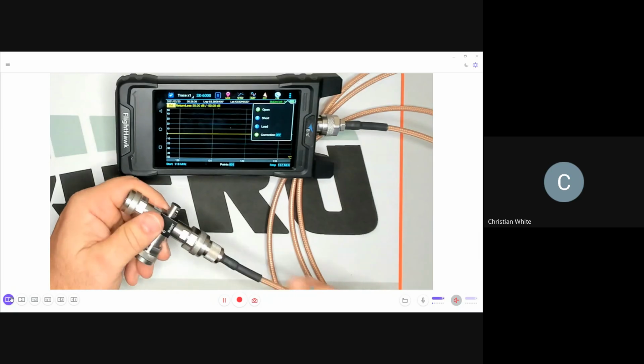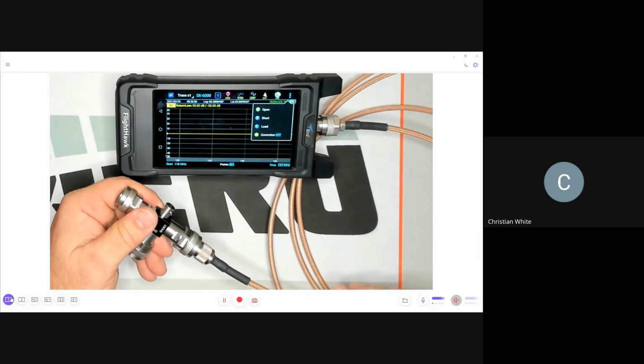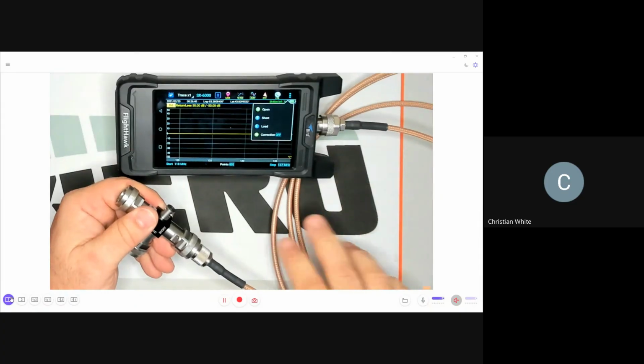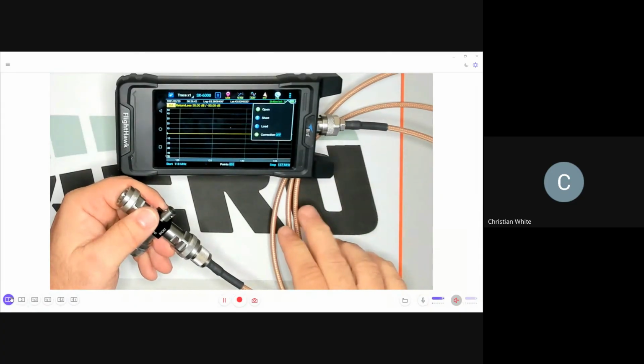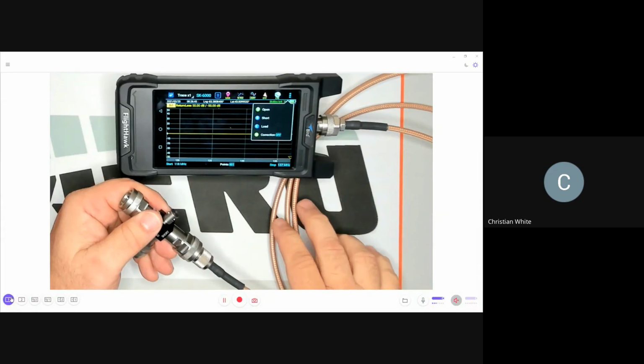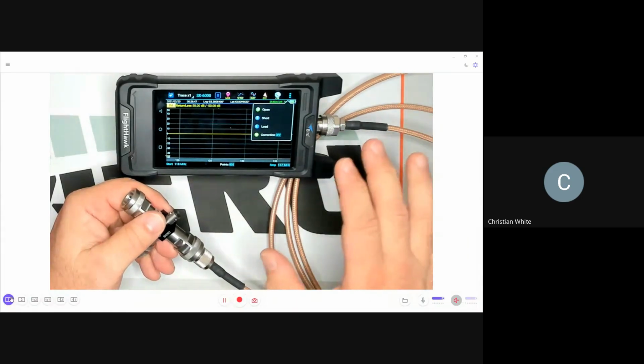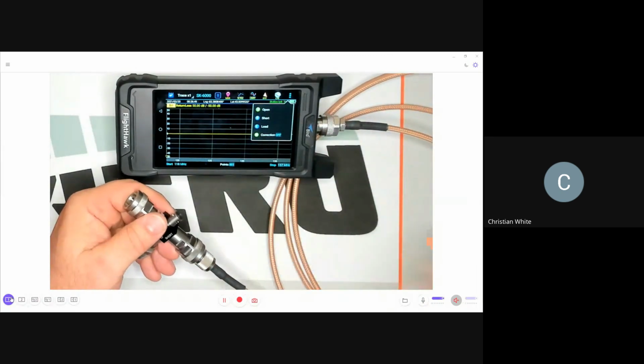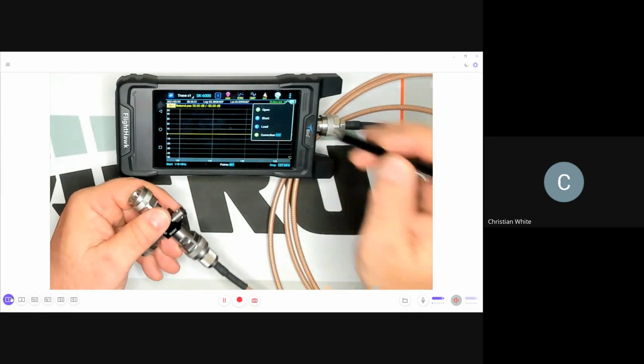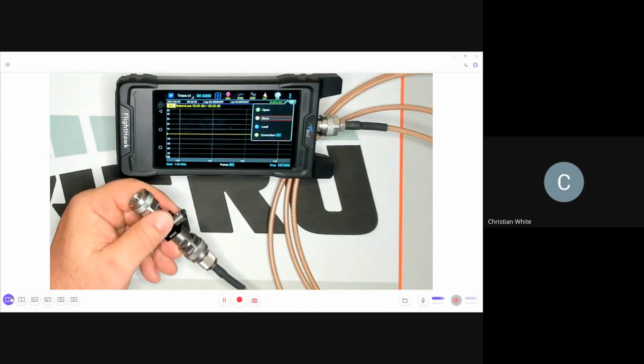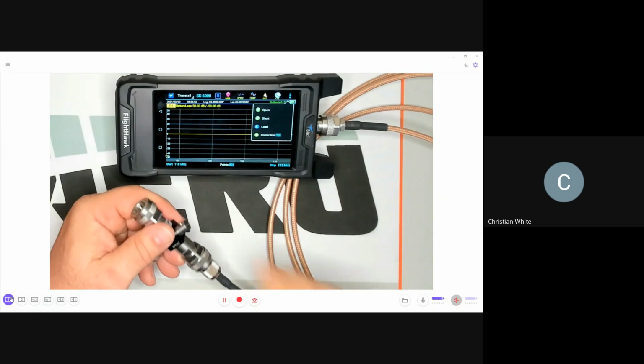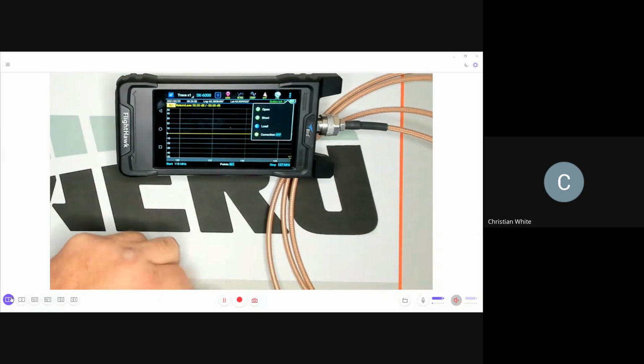Because what it's doing is calibrating it for that frequency, but it's also taking our lead into account. This is about an 8-foot, 10-foot lead. It's going to take our lead in and factor that out of the equation, calibrating the whole thing with our lead included. In this case, we're doing short, so we're going to click on short, give it a second, and it's going to turn green. Then we do our last one, which is our load.